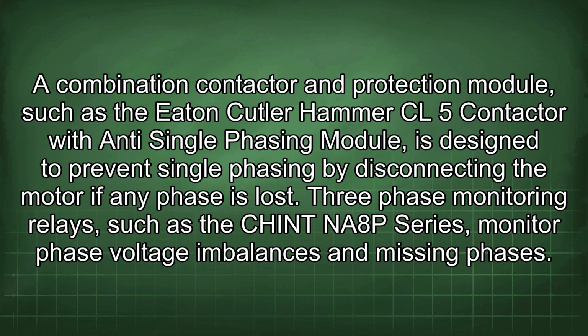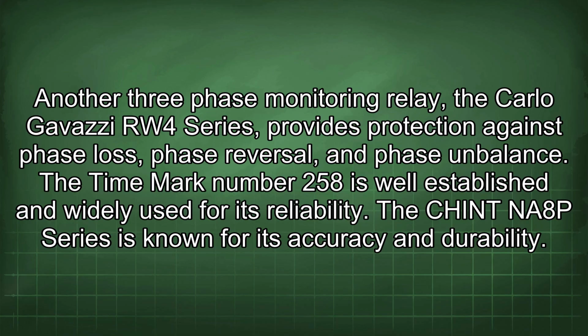A combination contactor and protection module, such as the Eaton Cutler Hammer CL5 contactor with anti-single phasing module, is designed to prevent single phasing by disconnecting the motor if any phase is lost. Three-phase monitoring relays, such as the Chint NA8P series, monitor phase voltage imbalances and missing phases. Another three-phase monitoring relay, the Carlo Gavazzi RW4 series, provides protection against phase loss, phase reversal, and phase imbalance.